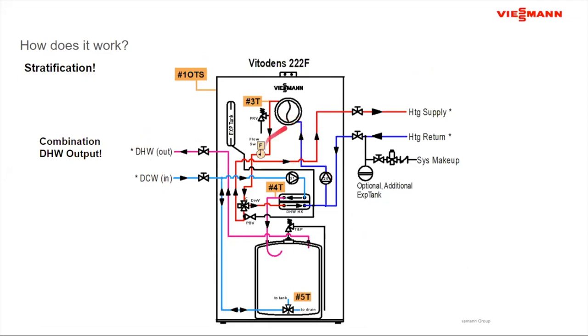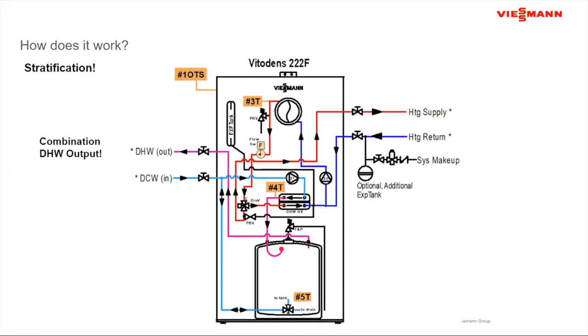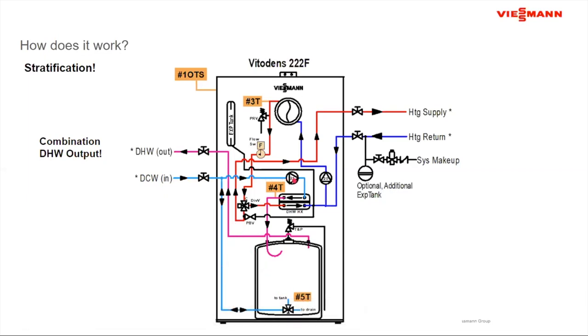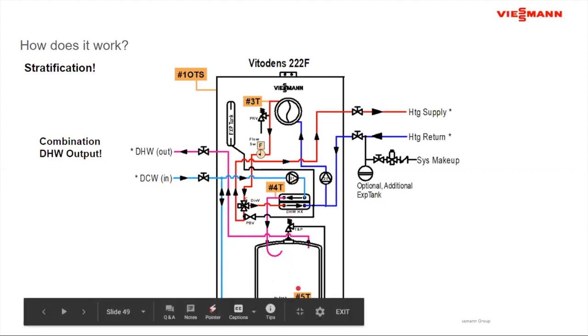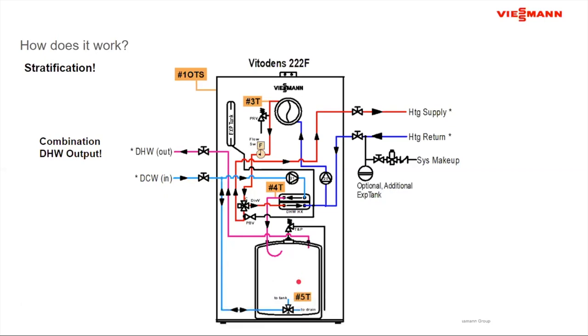The combi boiler normally is all about production. Here I have 26 gallons of water to draw against, but this also gives me instantaneous production of hot water to supplement it. So I can deliver a very large amount of hot water in a very short period of time because of this combination. Cold water can come into the bottom of the tank, or into the heat exchanger, or into both. Initially, we run off the storage of the tank until the number 5 sensor sees the water temperature. When that kicks in, it brings on the boiler, starts the pumps, shifts the valve over, and starts to produce hot water.